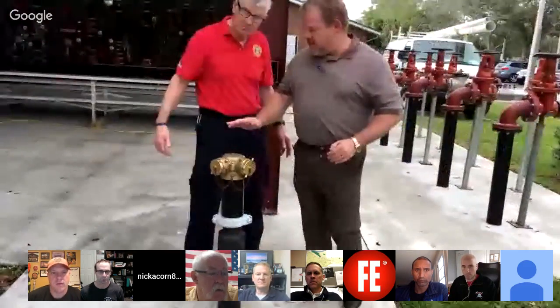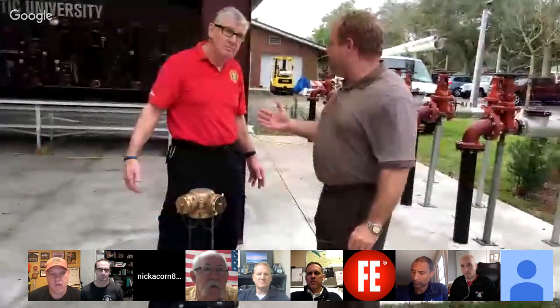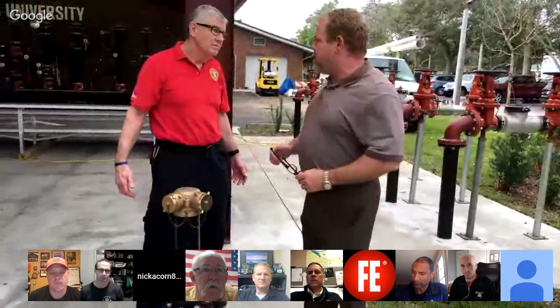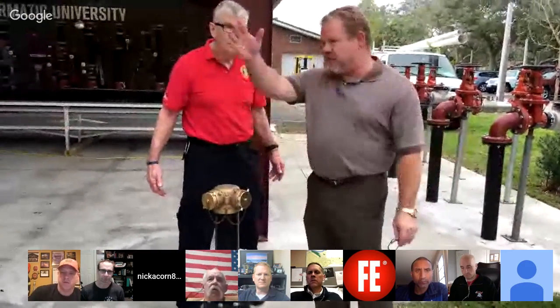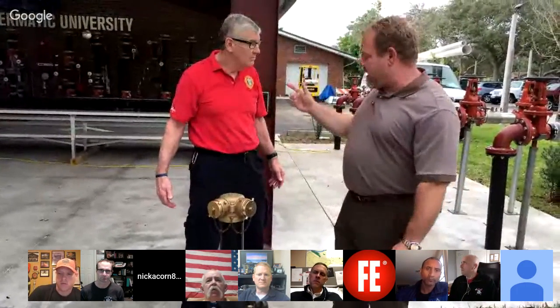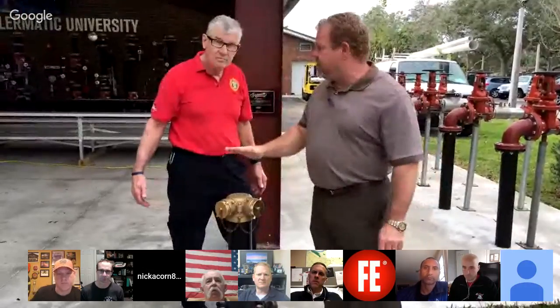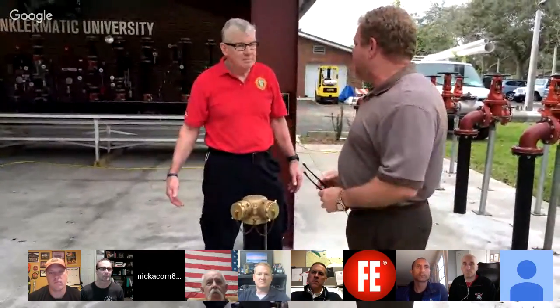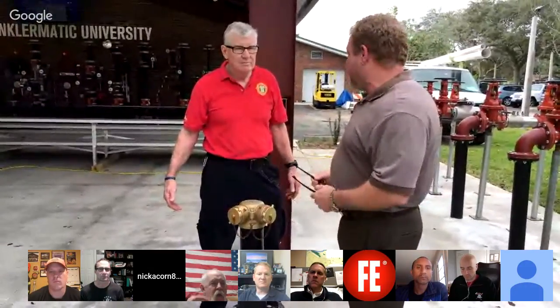So obviously this is a fire department connection, and essentially what we learned out in the field and what you just described, which the fire department would pull up, we can simulate a head, the fire pump activates, and essentially what we're trying to teach is control of the fire pump, right? So while the driver's connecting to the fire department connection, we walk in, we take a look at the fire pump, we're looking at the discharge side of the pressure, and essentially able to take control of the fire sprinkler system. So the fire department connection is connected to the discharge side of the fire pump, and it's effectively their command center, right?